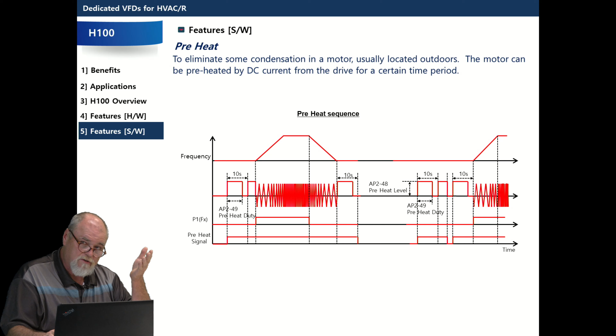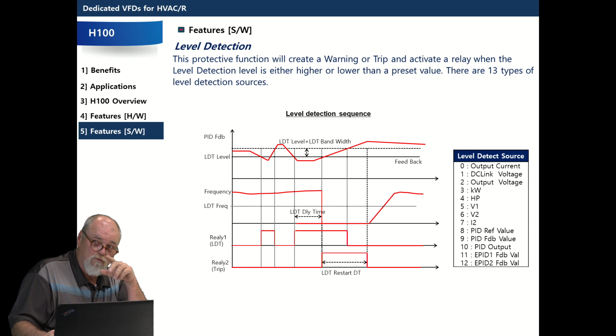We program the drive. These things are all stuff that was done by PLCs in the past. With our functionalities and what we can do today, we can do this in the drive, therefore removing PLCs. Plus, it's an open type of programming, very simplistic. It's in English. So for simple processes, this is where we're at. We can preheat motors. If you get conditions, in Nashville, I did one up there, they had 250 horsepower motors that they were concerned about condensation. So you would use the DC current run through the motor to dissipate it and not cause shorts.